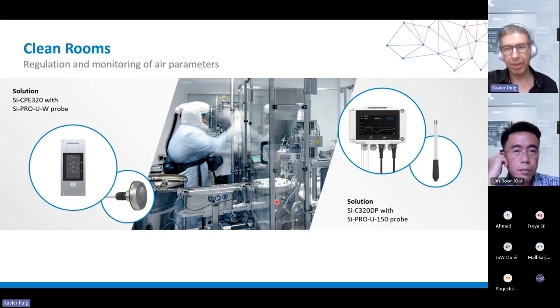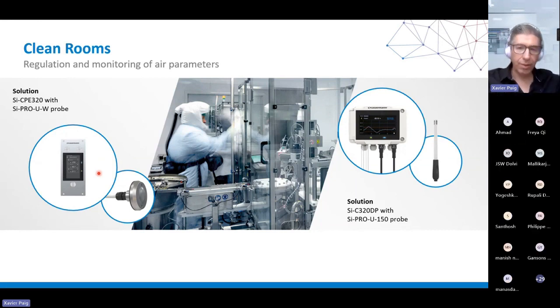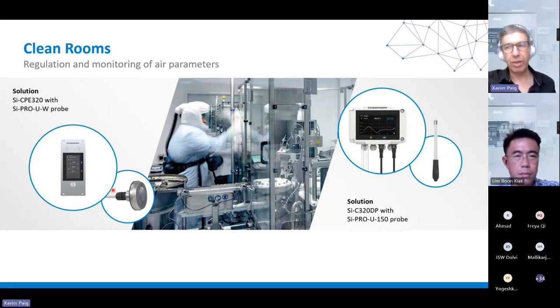So first application, clean rooms, typical for us. We can offer the CPE if the customer wants a local indication inside the clean room or on the door. Normally in clean rooms, you measure the differential pressure and humidity inside, plus temperature. So in this case, we can offer the CPE plus the new flush mounted probe. Those can be installed inside the clean room together, or for example the CPE outside and the probe inside. So from outside the clean room, before entering, you can easily read the value of the pressure and humidity as well. And the installation would be really neat because the probe is small and you don't really see it if you don't look at it. So it fits the clean room environment perfectly.